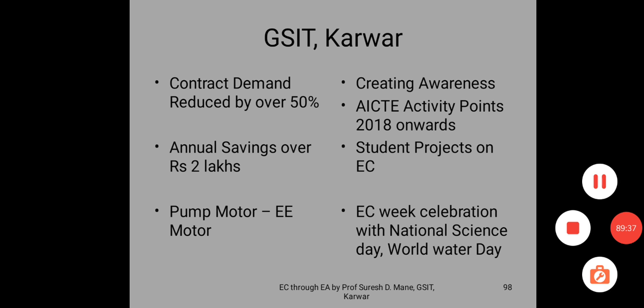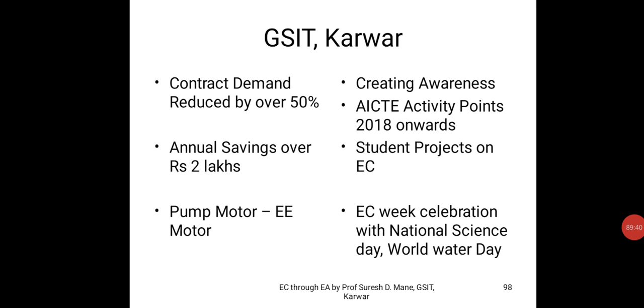Now coming to our institution, GSIT Karwar, when I took over, we saw that our contract demand was very high, but our actual maximum demand was low. I studied almost 2 years of earlier electricity bills, and we saw that our maximum demand was high and low, and contract demand was high, but we pay for the contract demand. Suppose our contract demand was 200 kVA and our actual maximum was 100 kVA, so we can reduce 100 kVA. Accordingly, 50% of the contract demand we have surrendered, and we are saving almost 25,000 rupees per month now, because per kVA they charge almost 200 rupees. So it is more than 2 lakhs per annum, earlier figure.